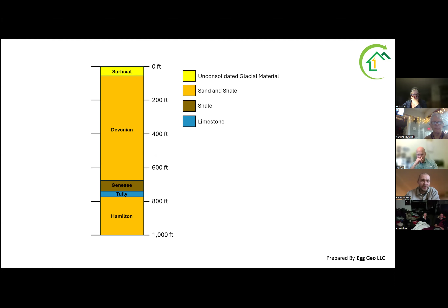First, the geology. There were some great publicly available reports on the geology for this side of New York. We're looking at a little less than 100 feet of surficial, unconsolidated material, with a large portion of sandstone and shale that's Devonian age, then a couple of small shale and limestone formations down into the Hamilton bedrock. We don't suspect drilling any deeper than 1,000 feet here, with some technologies as shallow as about 500 feet. That's about all the geology we needed to understand, and it's pretty typical for the area.